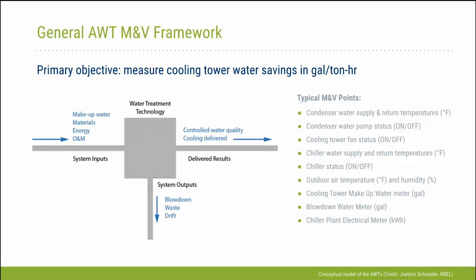So just to go over this framework of how we tested the technologies, it was fairly similar in most of these reports, but I just want to go over that really briefly. We pick a site that makes sense and they're nice enough to host the technology there. We go out to the site and we decide, depending on what savings we're trying to measure, whether it's water, chemicals, energy, what our target metrics are, what it is we're trying to achieve. We put instrumentation on the system: flow meters, temperature meters, CTs to measure energy from chillers and cooling towers, depending on what we're trying to find out. We measure the makeup water coming in. We measure energy in some cases. In this case, we measured energy. We look at O&M, what was the cost of operations and maintenance of the system prior to the technology and post-technology. We measure blowdown systems, waste. We estimate drift losses of the cooling towers.